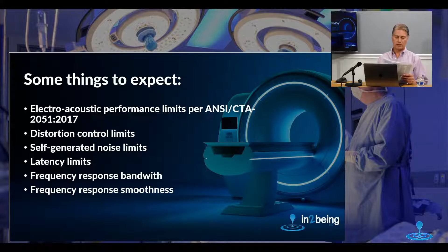And actually, since we do have just a minute here, I want to tell you just a bit about some of these areas that we weren't necessarily going to put into the slides, if we can find them here. You've got distortion control limits, self-generated noise limits, latency limits, frequency response bandwidth, and frequency response smoothness. And this is interesting because FDA says distortion control has to do with how faithfully the device reproduces frequencies. So it's a question of how high fidelity the sound is. And if you've ever encountered somebody with an older hearing aid, you know that was a problem historically.